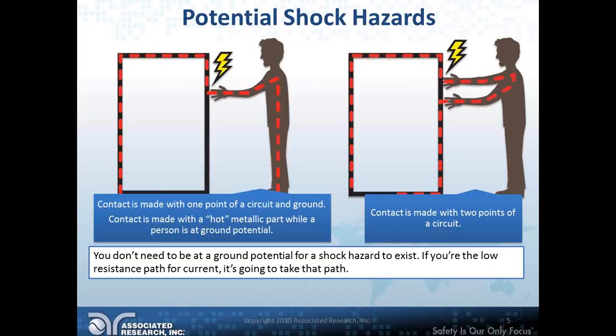The takeaway I want you to get is this: a lot of people, especially those who've worked with electrical equipment, realize you don't necessarily need to be at a ground potential for there to be a shock hazard. Even if you've isolated yourself from ground potential, you still have to be wary, because if you're providing a low resistance path for the current to travel, it's going to take it. You're the path, basically, is what this comes down to.